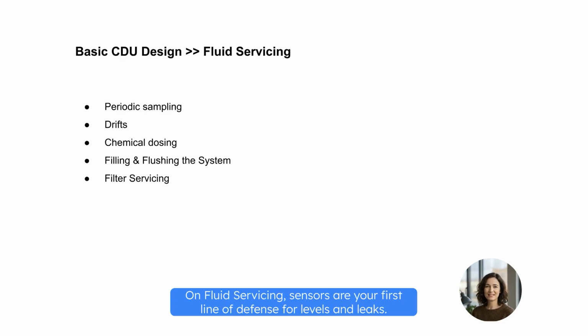On fluid servicing, sensors are your first line of defense for levels and leaks. But they don't tell the whole story. You must perform periodic sampling to assess the actual chemical composition. Over time, fluid chemistry drifts. When this happens, you need to intervene with chemical dosing to rebalance the loop. Always follow the fluid vendor's guidelines. Never improvise with the chemistry.